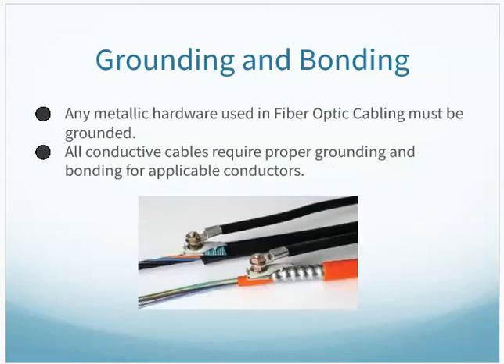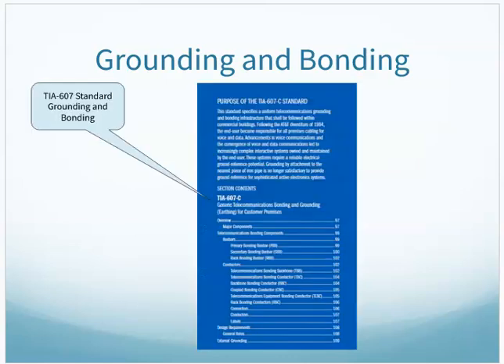And again, if we do have any fiber optic that has shielding or armoring on it, that would also need to be grounded in our closets. So I might need to worry about that with my fiber install. 607 has the grounding and bonding requirements that I would worry about.